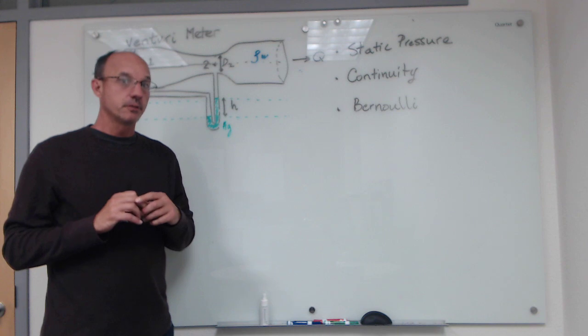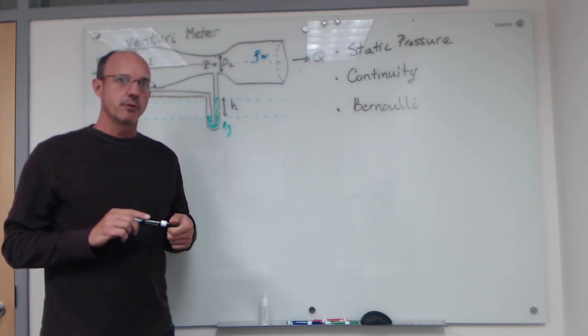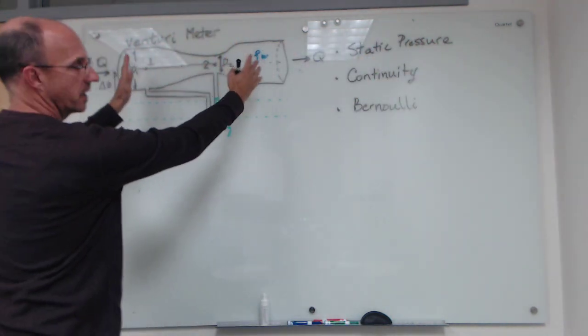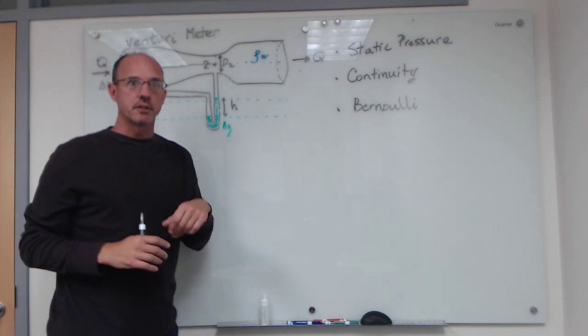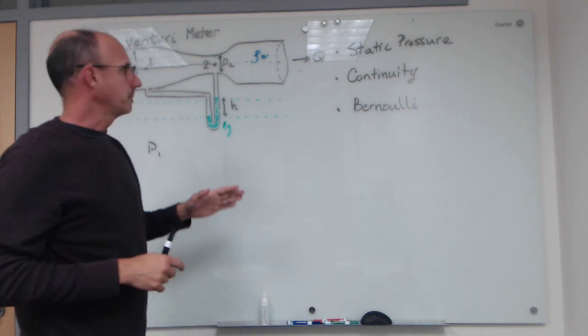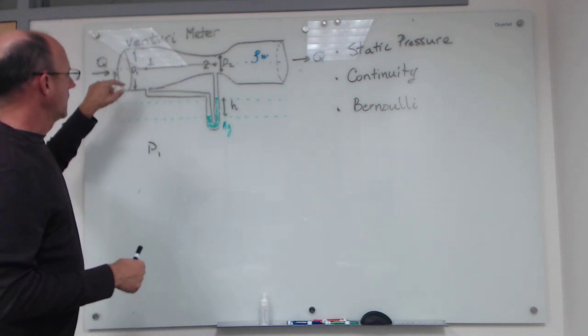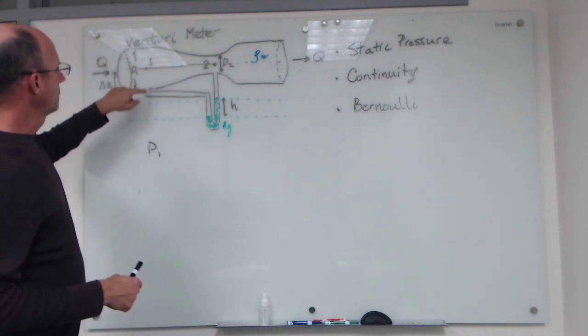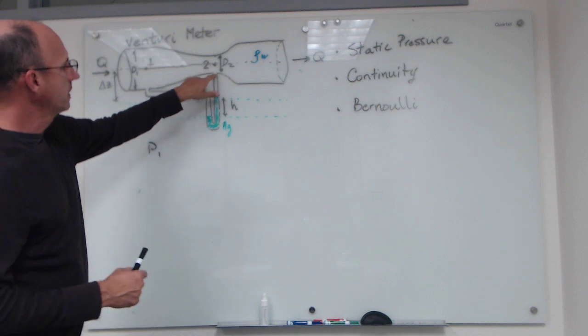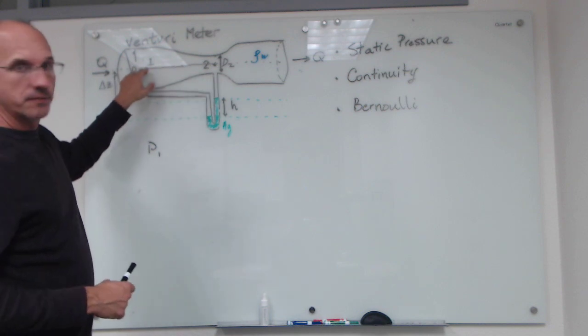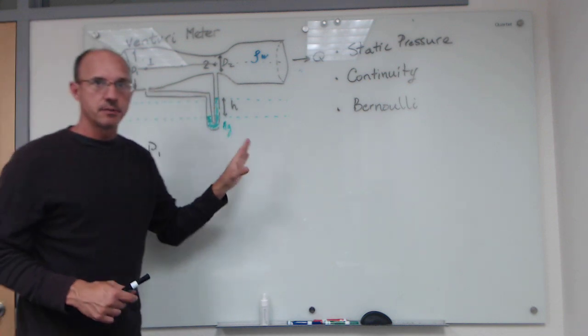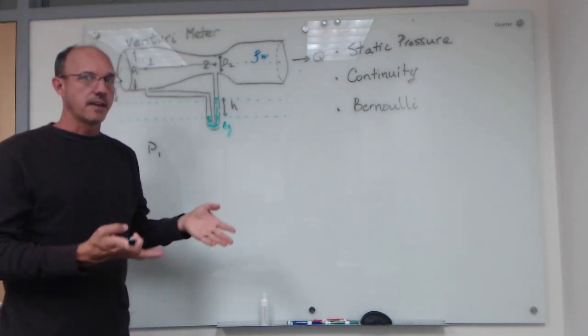In this video we're going to look at how flow is measured in a pipeline with a Venturi meter. The idea is that if you have a long pipeline moving fluid, in one section of the pipeline you can put this device called the Venturi meter, and all the flow will have to go through this constriction. By measuring the difference in pressure between two points with a manometer reading, you get precisely what you need to correlate with the flow rate.